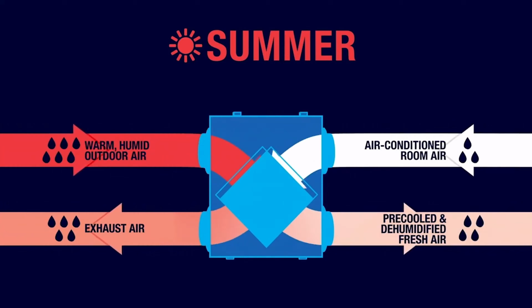Most homes need about 0.35 air exchanges per hour, which means roughly a third of the indoor air gets swapped out each hour. In the case of our home here, it's 3,300 square feet, so we'll need an ERV rated for at least 154 CFM. For this, I like RenewAire ERVs, which have models that provide the necessary CFM and help keep the indoor air quality in check. So now the ultimate smart home has a heating and cooling system that is both efficient and comfortable. The air quality will be excellent and we can maintain comfort all year long, even in the harshest conditions.